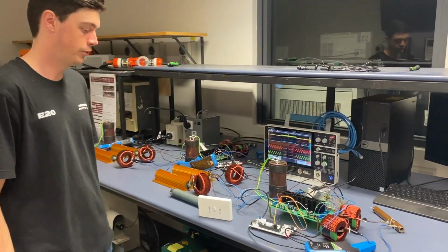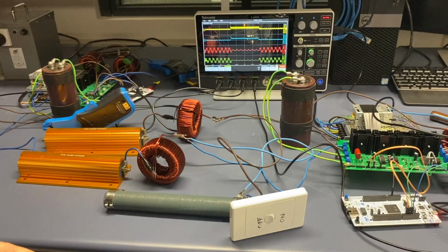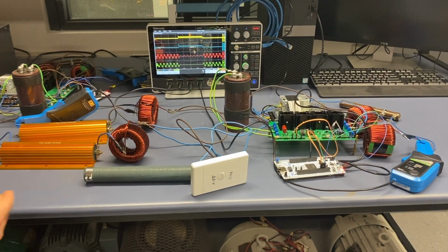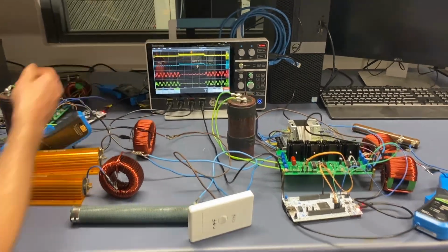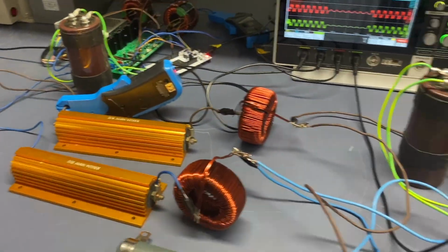So now we've moved our fault to zone 2, which is just before terminal 3, and you can see that with our new measurements both spikes are positive. This is because the current is going through both current meters towards zone 2 and towards the fault.